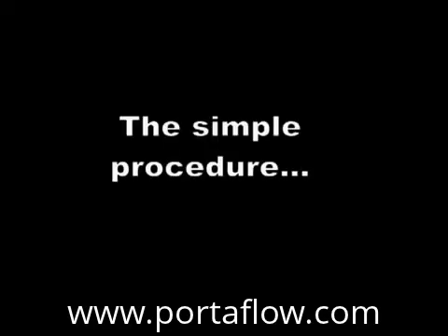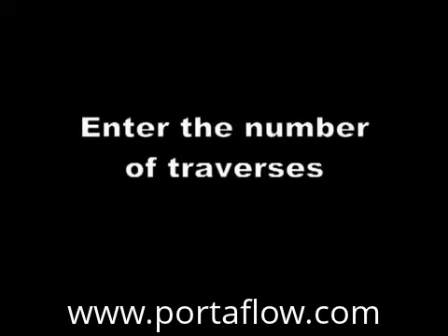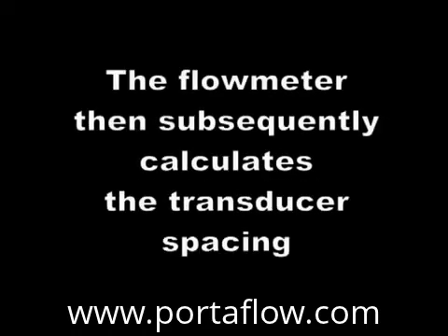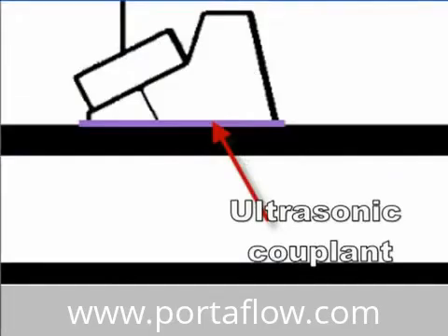All of this complexity boils down to a pretty simple procedure. Step 1: enter the pipe material, diameter and wall thickness, or nominal diameter and pipe schedule. Step 2: enter the fluid type. Step 3: enter the number of traverses. The flow meter then calculates the transducer spacing. We then place the transducers on the outside of the pipe at the spacing calculated by the flow meter. We also need to place an ultrasonic couplant between the transducers and the pipe, because an air gap will stop the ultrasonic signal.